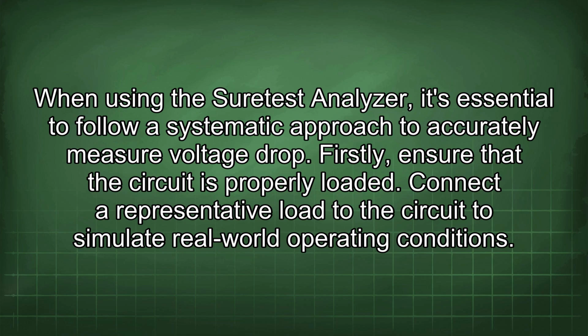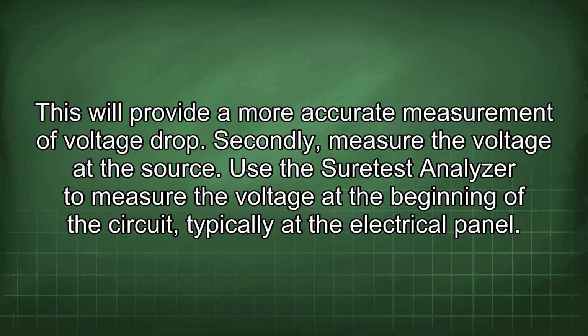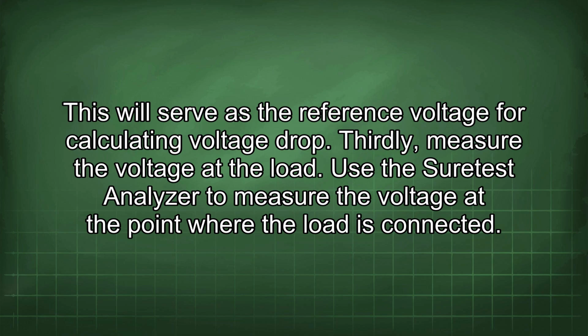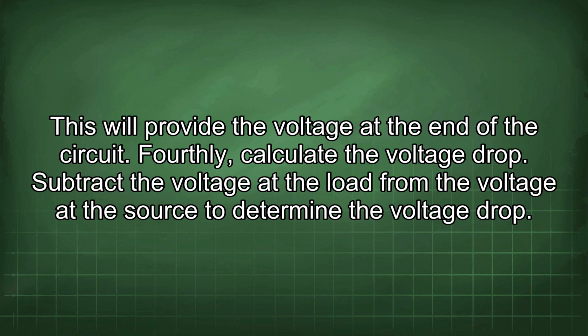Firstly, ensure that the circuit is properly loaded. Connect a representative load to the circuit to simulate real-world operating conditions. This will provide a more accurate measurement of voltage drop. Secondly, measure the voltage at the source. Use the Suretest Analyzer to measure the voltage at the beginning of the circuit, typically at the electrical panel. This will serve as the reference voltage for calculating voltage drop. Thirdly, measure the voltage at the load. Use the Suretest Analyzer to measure the voltage at the point where the load is connected. This will provide the voltage at the end of the circuit.